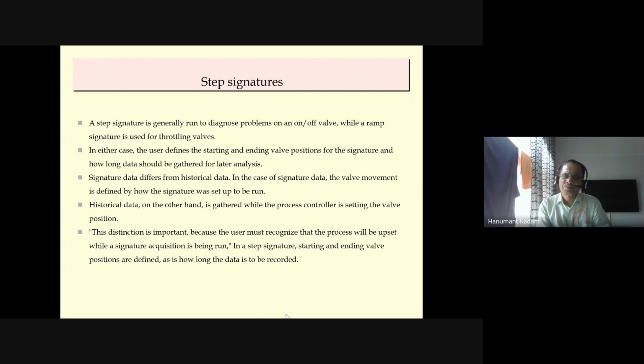When the valve goes from off to on, that change time is also measured. You can plot the graph of the signature. Signature data differs from historical data. Earlier, when the valve is new, there is a certain time required for changing from valve on to off. But after some days of use in the plant, due to hysteresis and other mechanical degradation, this data changes. In the case of signature data, the valve movement is defined by how the signature was set up to run. Historical data, on the other hand, is gathered while the process control is setting the valve position. So you'll get its history.